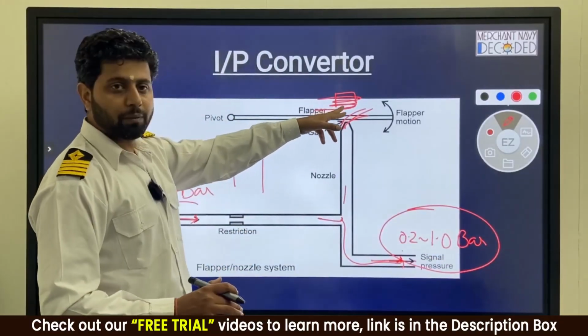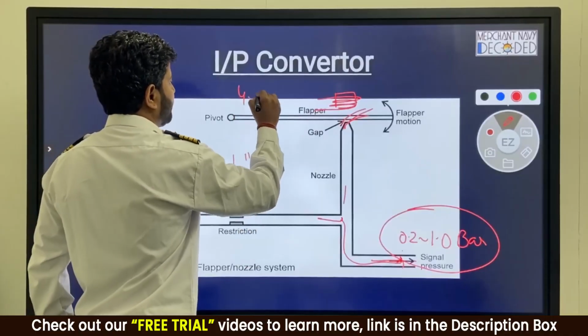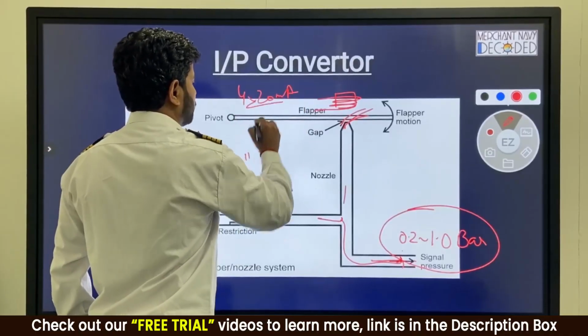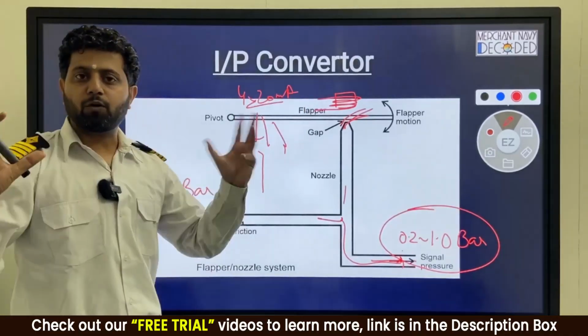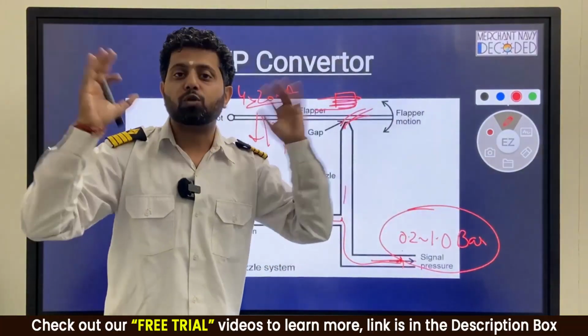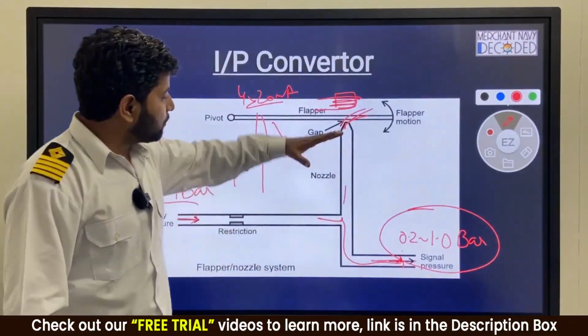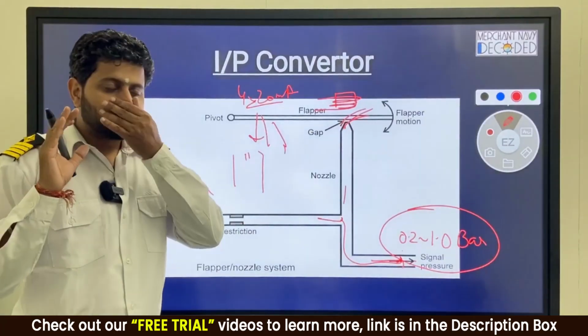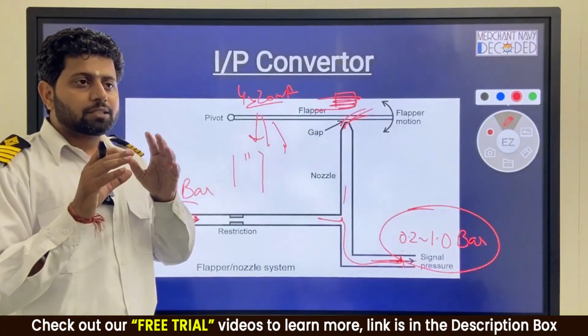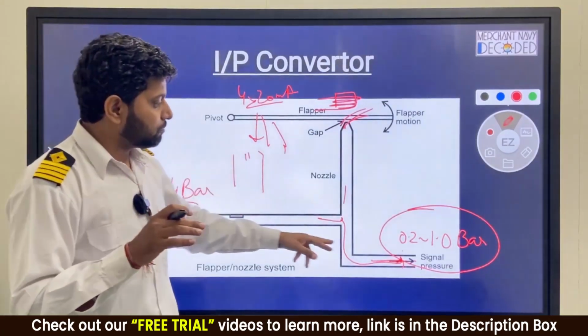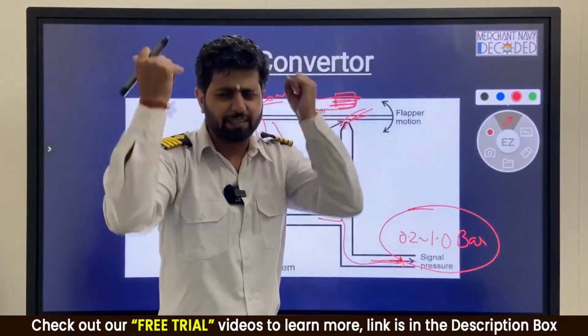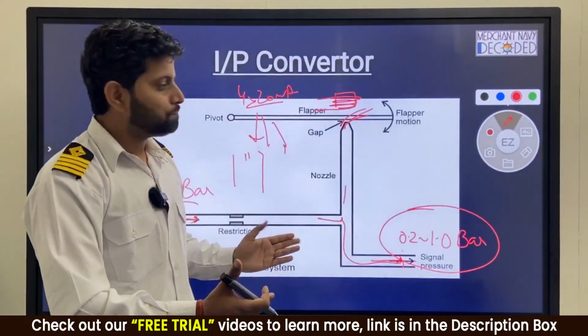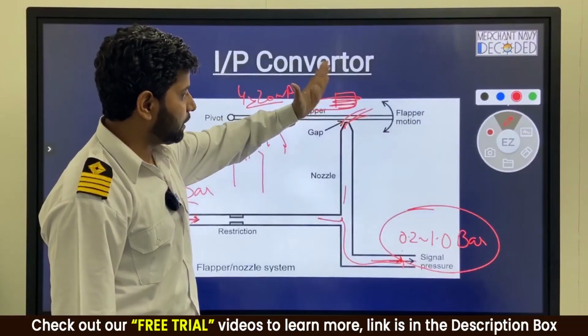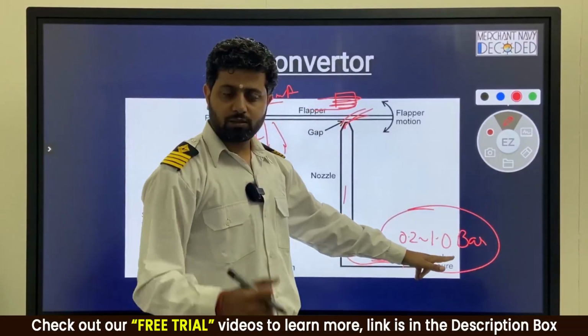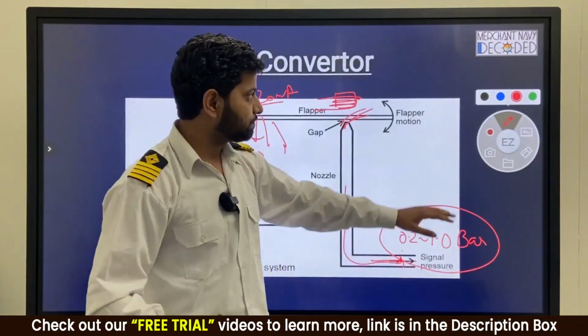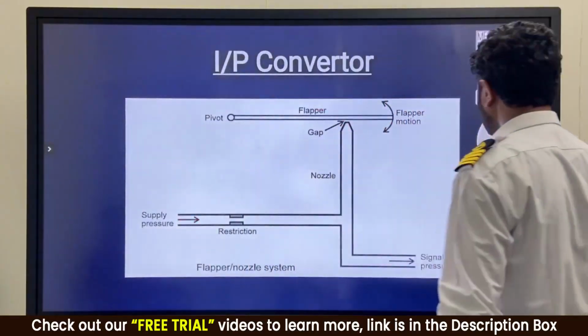And the current coming over here is 4 to 20 milliamps, which is coming from the photo cell or XYZ, whichever thing we want to calculate, or from the unbalanced Wheatstone bridge. Copied? So the unbalanced Wheatstone bridge says, bhaiya, the current is less, that means we want more air. Maybe we want to open the valve or close the valve, XYZ whatsoever. I'll be explaining that later in the video. So accordingly, this flapper nozzle will operate, and accordingly the signal, the amount of air we need, will increase or decrease. Let's move ahead and understand further.